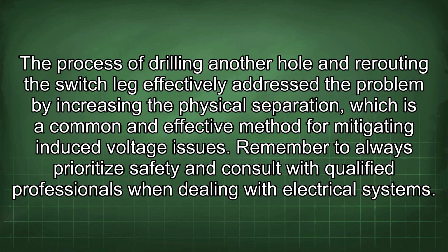The process of drilling another hole and rerouting the switch leg effectively addressed the problem by increasing the physical separation, which is a common and effective method for mitigating induced voltage issues. Remember to always prioritize safety and consult with qualified professionals when dealing with electrical systems.